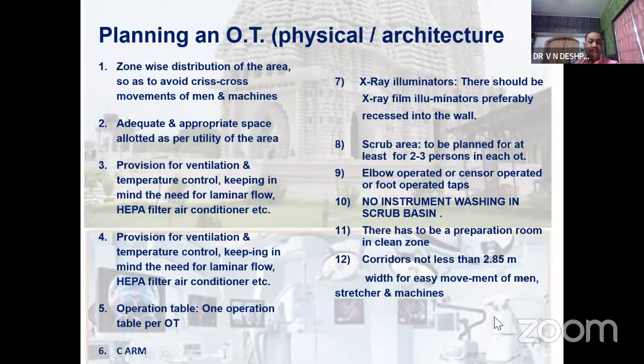Provision for one operation table per OT has to be there. We have to plan for X-ray illuminators and scrub areas—the scrub area may be for two or three persons. As Sushrut rightly said, there should be a separate scrub station or scrub basin for each surgeon, and we must decide whether to go for elbow-operated, sensor-operated, or foot-operated taps.